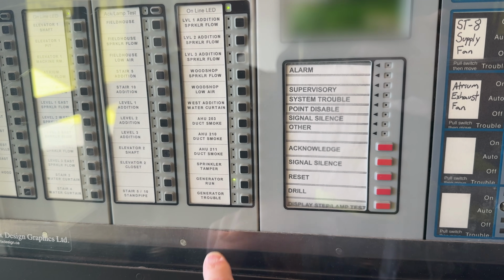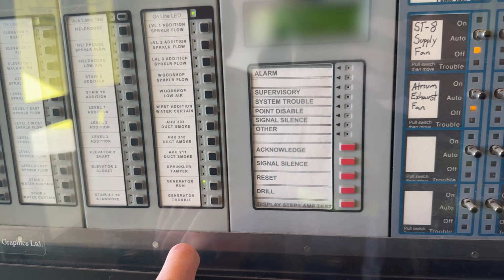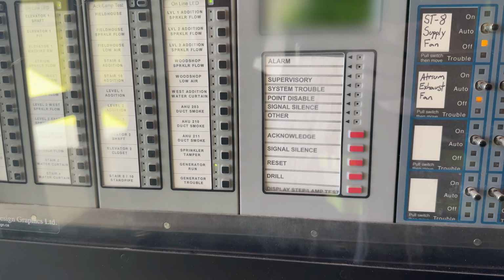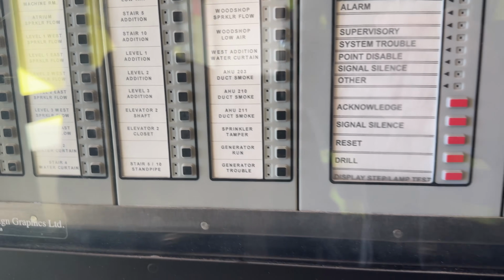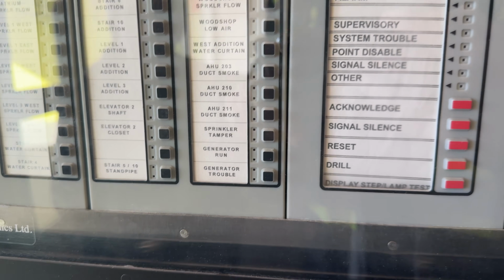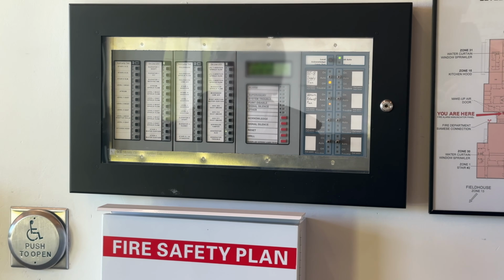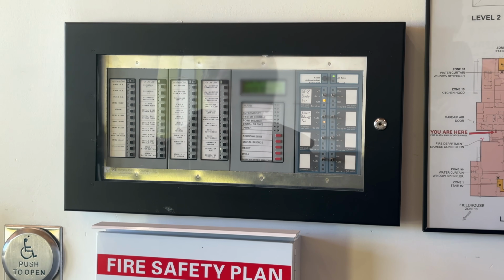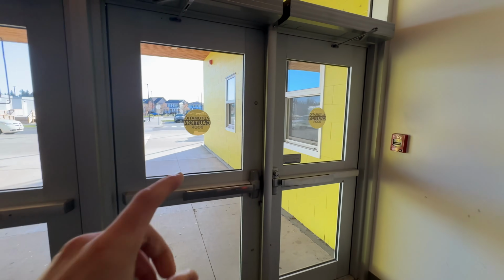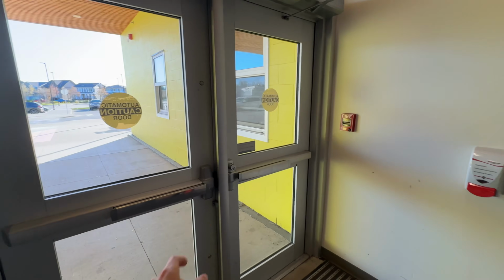Maybe the trouble's audible, not run. No, it should be put into an audible supervisory. That's what it usually does. I guess maybe that's fine as long as it realizes it's running. So I think that could be it, that it's set to an equipment monitor, so it's not audible like the doors are. Because these doors here are monitored for their position by the fire alarm, if they're open or not. It just doesn't actually show up on there.